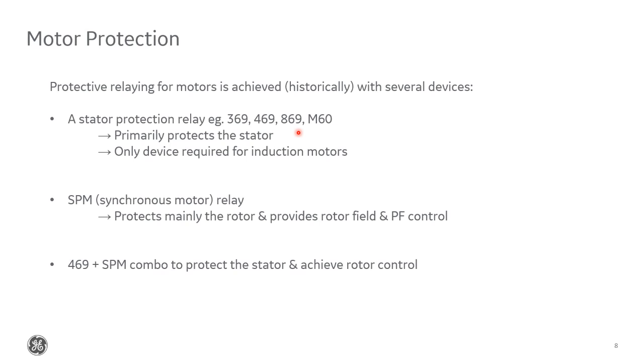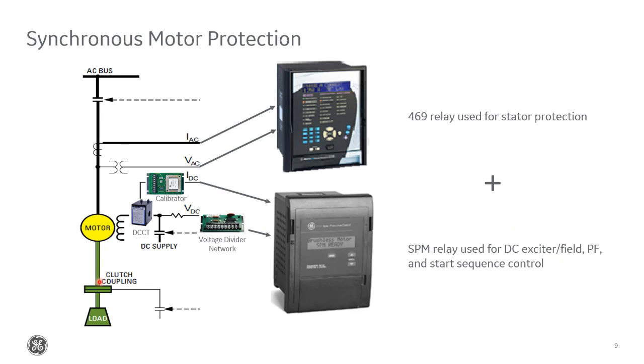So typically, we have one of these relays for stator protection if we have a synchronous motor. And then to provide the field protection and start sequence control, you know, the controller that decides when the DC field can be applied and signals the contactors, we would use our SPM relay, which was a dedicated rotor protection and control relay for synchronous applications. Most often, what we tend to see installed is a 469 relay with an SPM directly beside it. So that's what we see here. We have the 469 relay on the top and the SPM relay on the bottom.